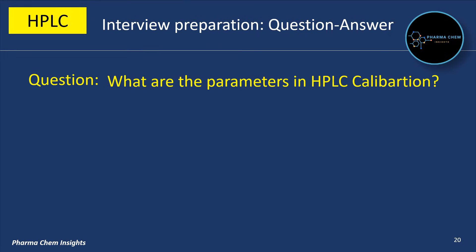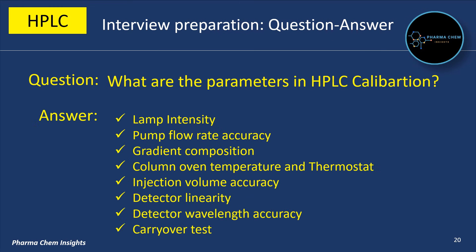What are the parameters in HPLC calibration? These are the parameters in HPLC calibration: first is lamp intensity, second is pump flow rate accuracy, third is gradient composition, then column oven temperature and thermostat, injection volume accuracy, detector linearity, detector wavelength accuracy, and carry over test.